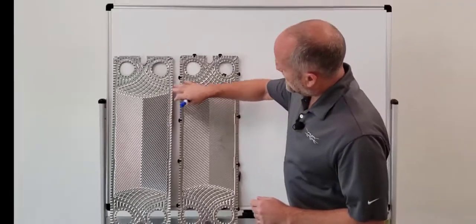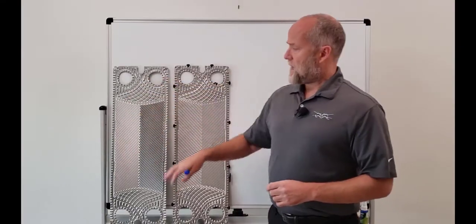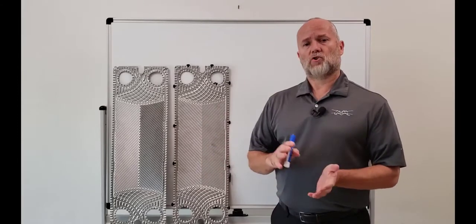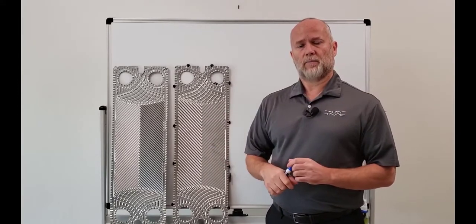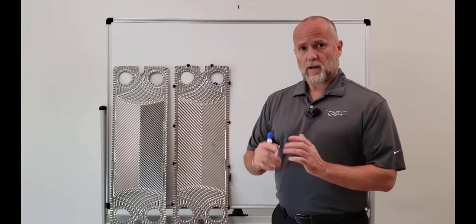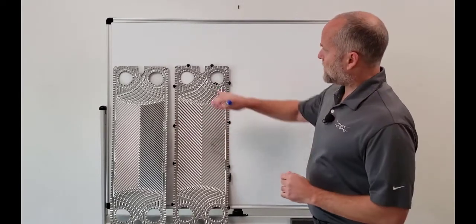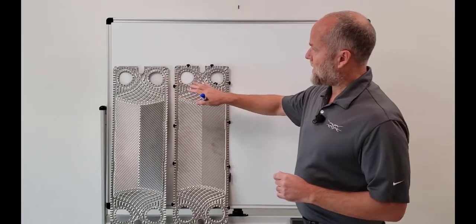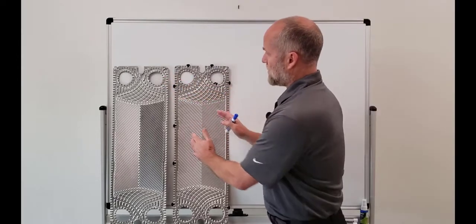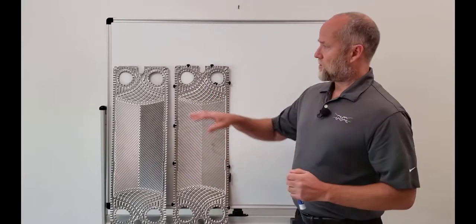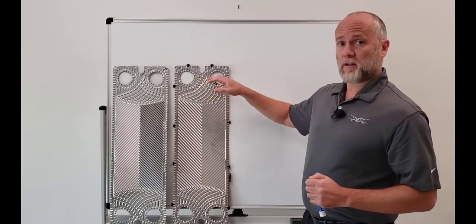This is the gasket groove, and it's not just a bend in the plate. Actually, it is carefully designed to make sure that the pressure applied on the gaskets seals the heat exchanger when you compress them. And of course, this is where the plate hangs from the carrying bar. The hardest part in designing a plate is to make sure that the distribution is even across all the surface, taking into consideration that the inlet port is offset.